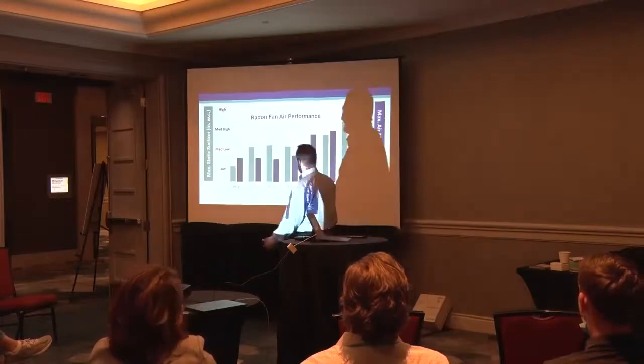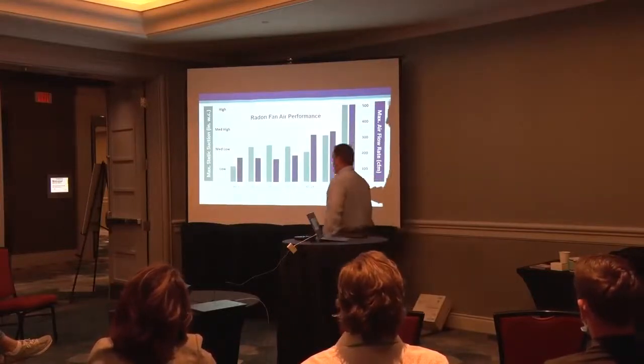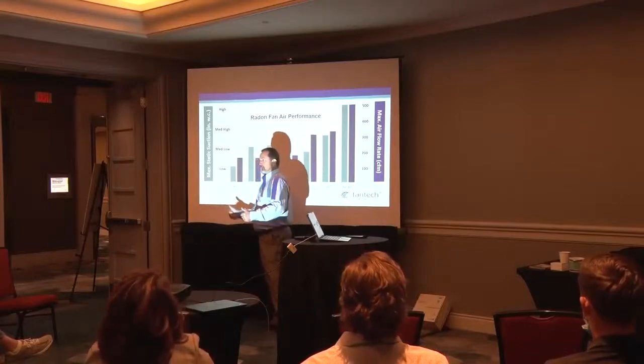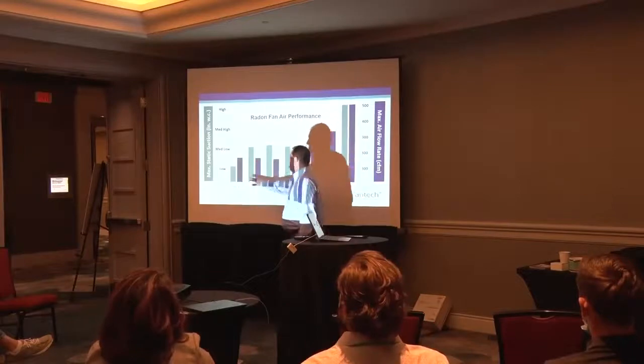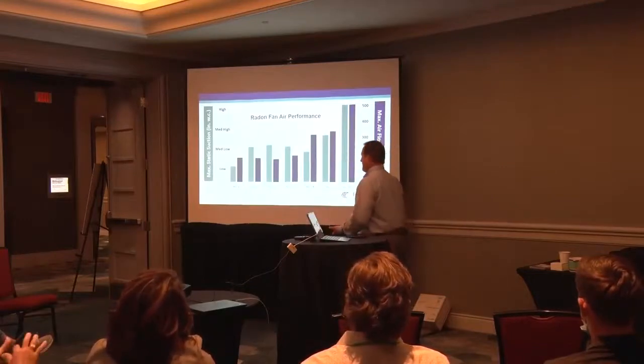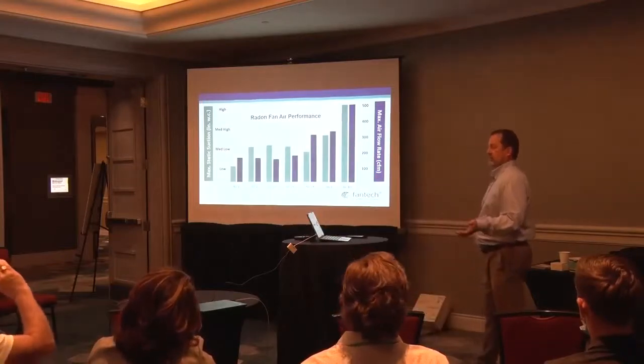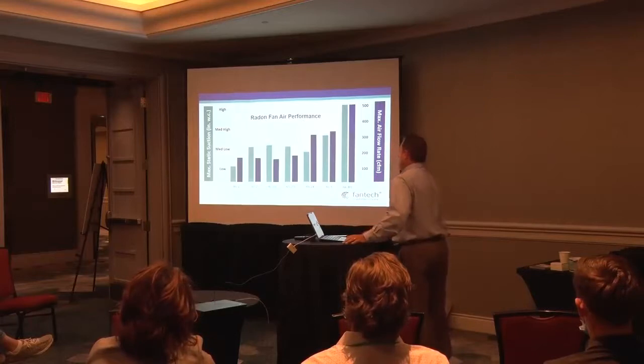Every fan has the ability to move air against resistance. In the radon world, we're most often concerned about creating a certain suction to achieve pressure field extension and prevent radon from entering the building. Sometimes airflow is also a primary concern. Radon fans tend to have a very steep fan curve because suction is generally so important — they're typically working at static suction levels much higher than, say, an HVAC fan.